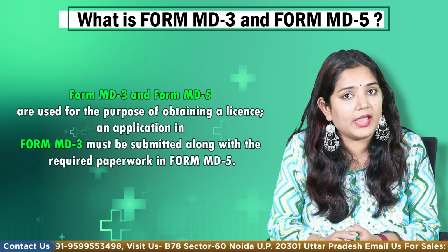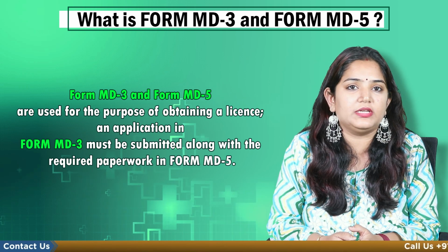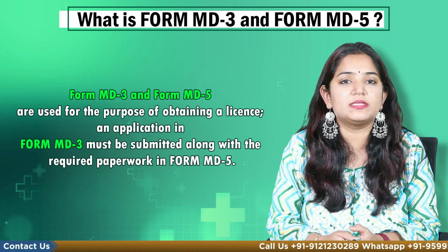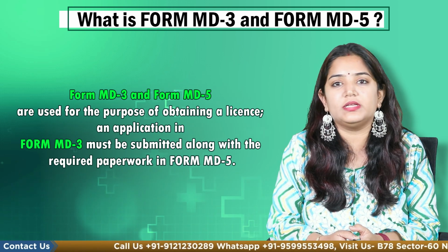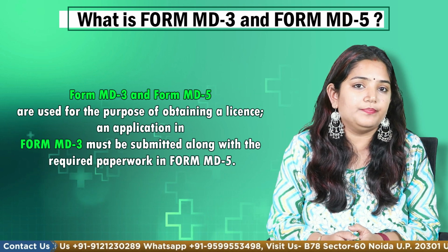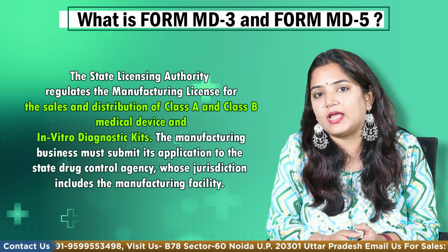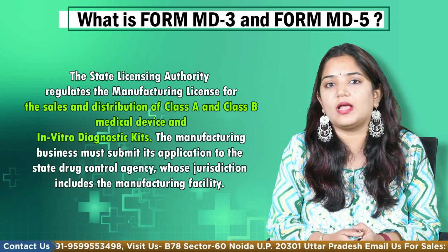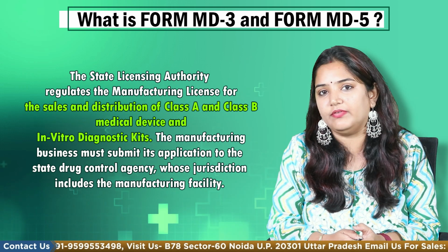Form MD-3 and MD-5 are used for the purpose of obtaining a manufacturing license. An application in Form MD-3 must be submitted along with the required paperwork, and the approval is in Form MD-5. The state licensing authority regulates the manufacturing license for the sale and distribution of Class A and Class B medical devices and in vitro diagnostic kits, that is IVD.